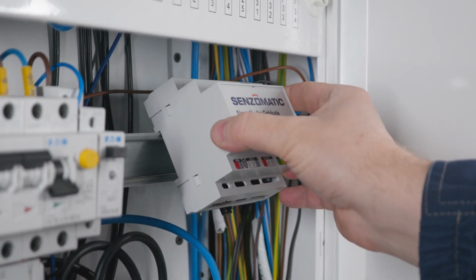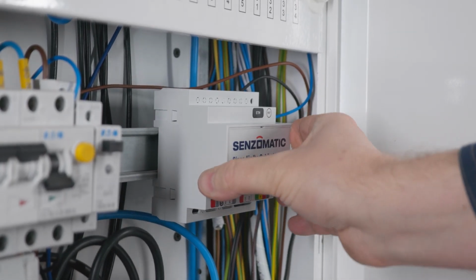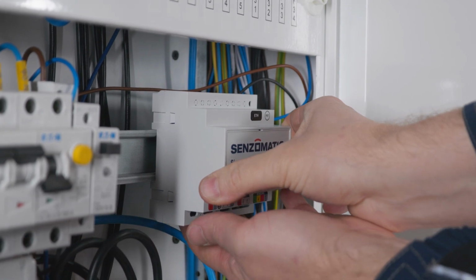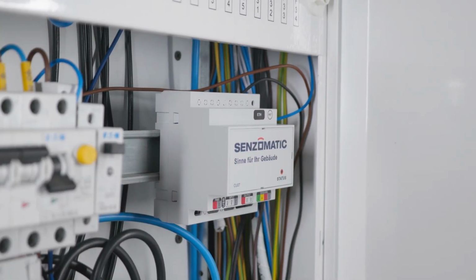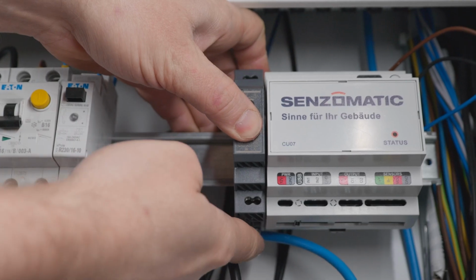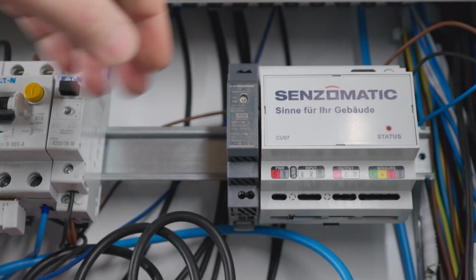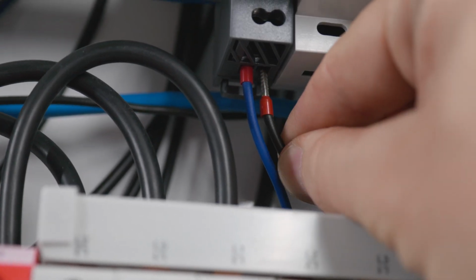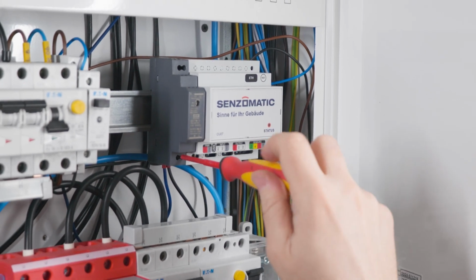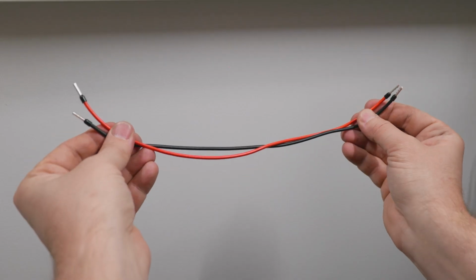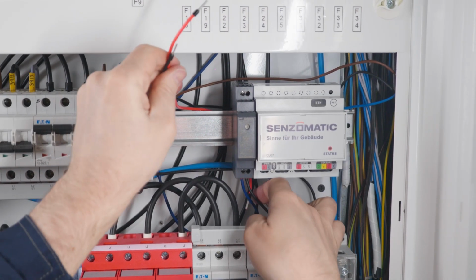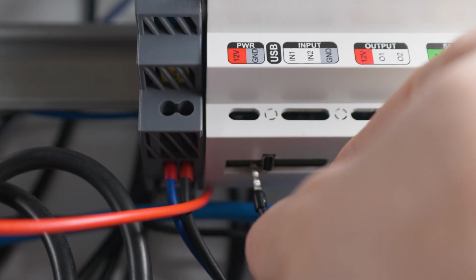The modules are mounted on the DIN rail by hooking the device on its top edge and then snapping it in at the bottom. Always position the power source to the left of the unit. Now connect the phase and neutral wires to the power source. Then connect the 12-volt power supply to the central unit. The power supply is connected to the lower left corner of the terminals.